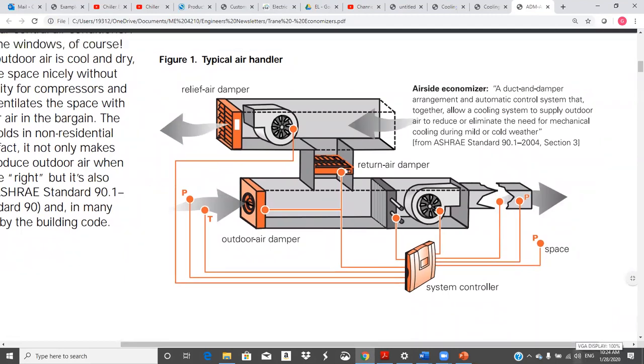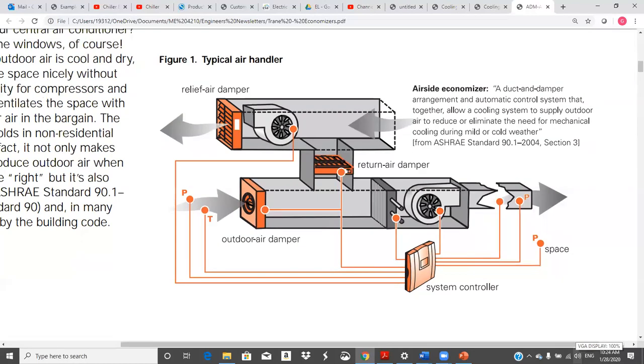Okay, that's pretty good. So, simple, like a single zone air handler. We just have one space temperature out here, sending information back to the controls. We got supply air being blown out by the fan. And that air temperature, what's a good supply air temperature? What kind of temperature are we looking for to blow in here in the summertime to keep this space comfortable? Any idea? What's that? 56. Yeah, that's pretty darn good.